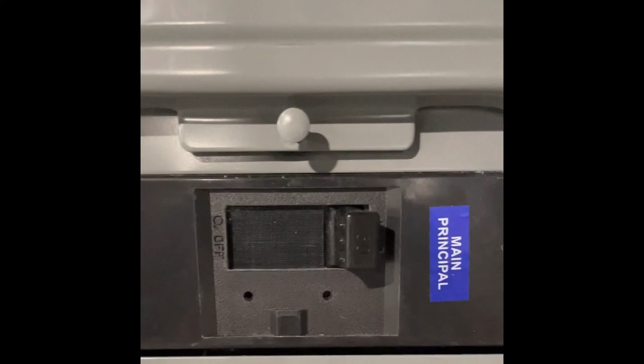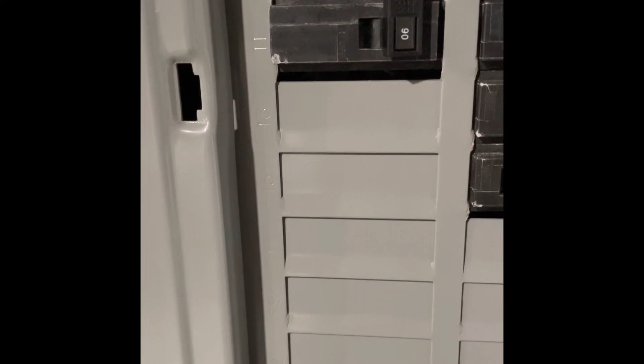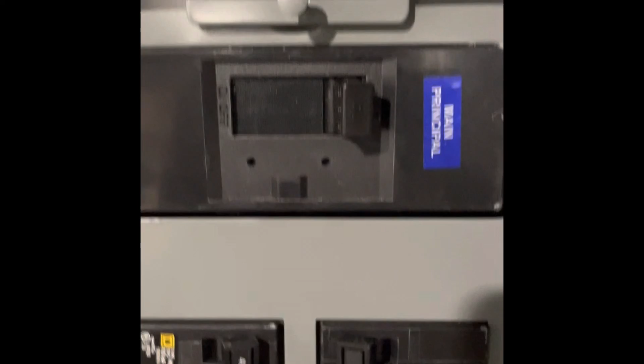But the problem with this setup is that there is additional equipment needed. As you may have guessed from the previous video, the equipment needed is safety equipment that is missing to protect the utility grid workers. What is missing? Well, just to remind you, this 90 amp breaker is where electricity from the solar system comes into my main panel. And this main breaker is the last stop before that electricity would be back-fed into the utility grid.